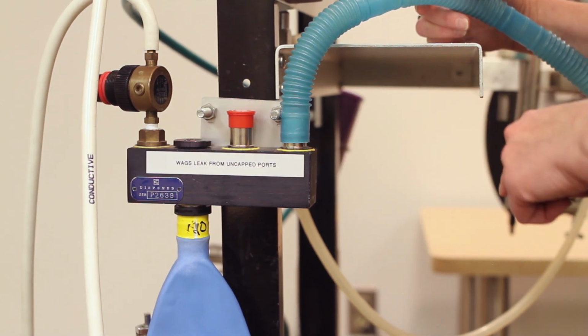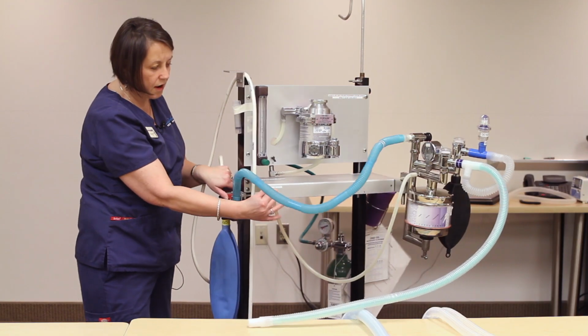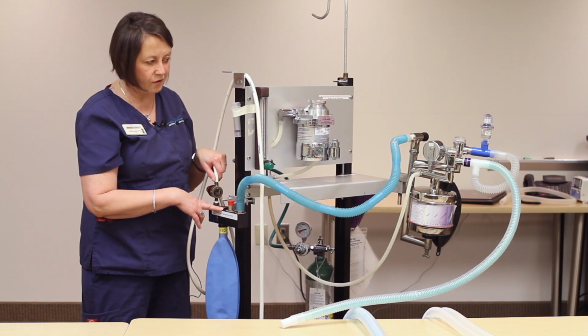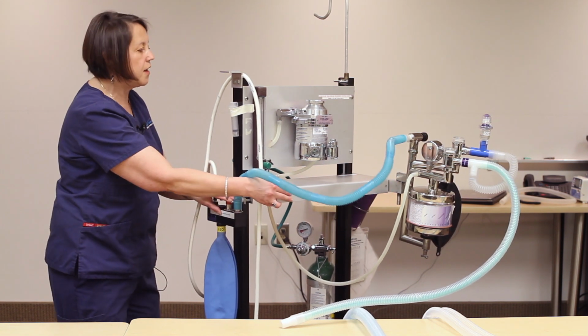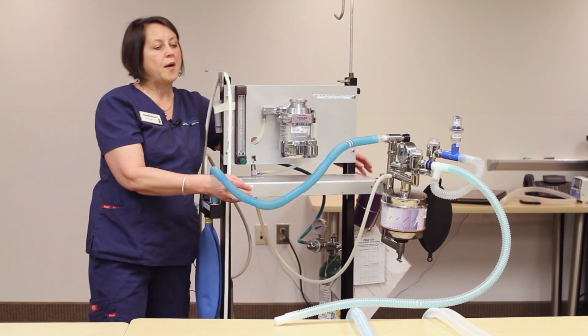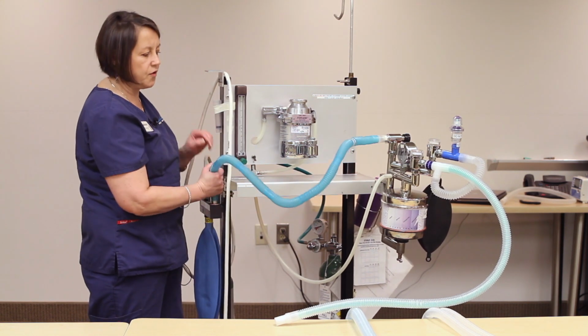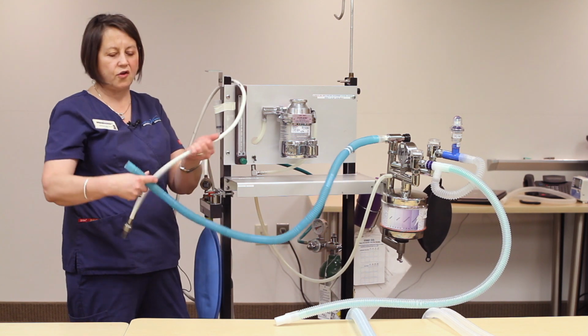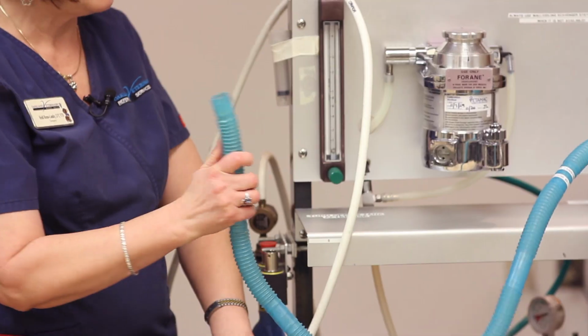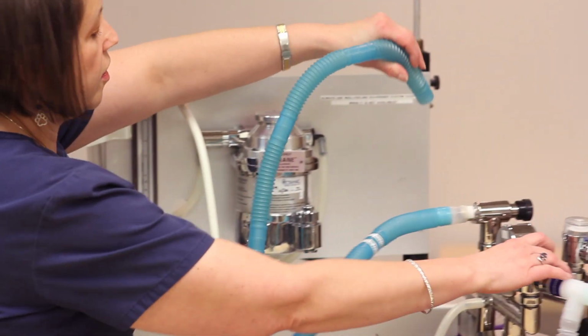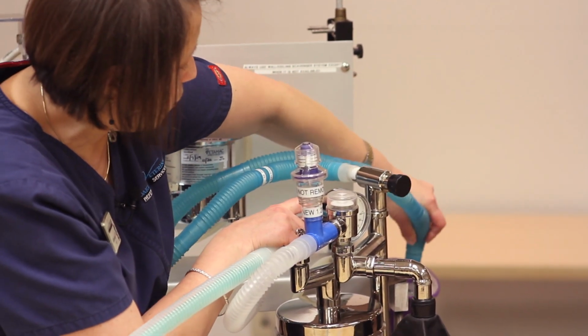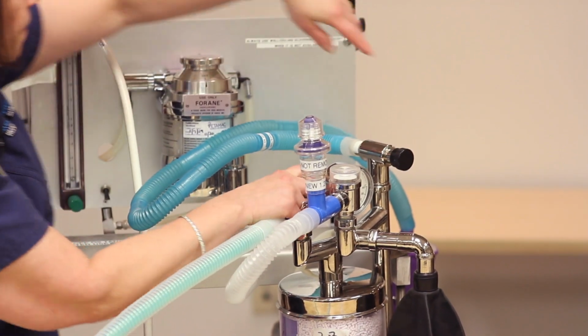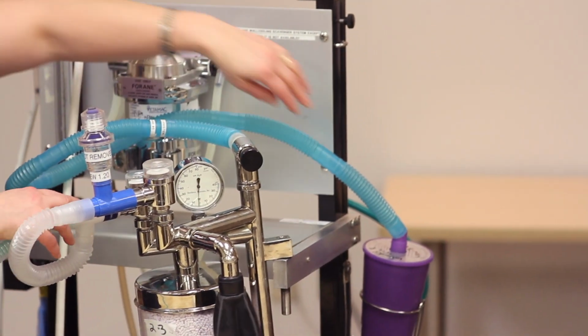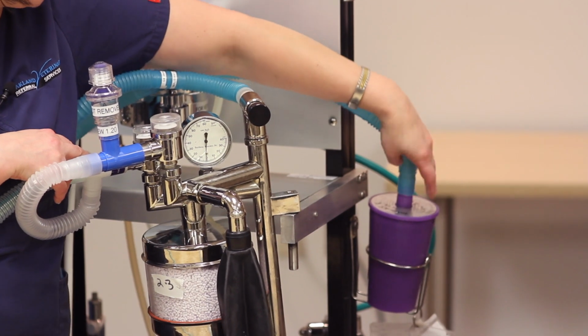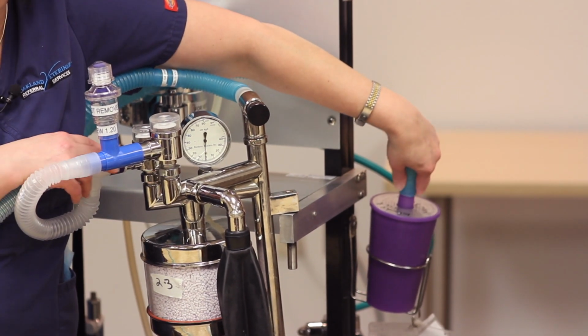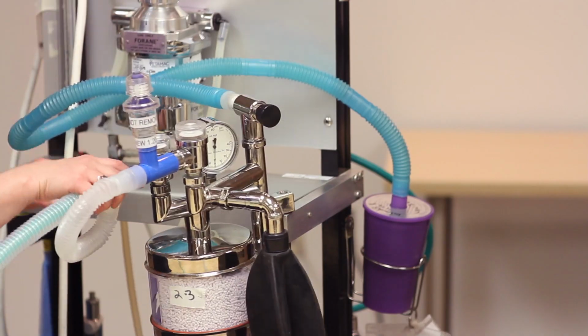And ideally, you always want to use your active scavenger interface whenever possible, since these F-air canisters are only good for about 100 to 120 grams. But if you need to use it, if you don't have access to your ceiling scavenger, you would go ahead and make sure that you plug your scavenging hose into your F-air canister. The F-air canisters do always have to remain in an upright position, so they should never be placed on their side or anything like that.